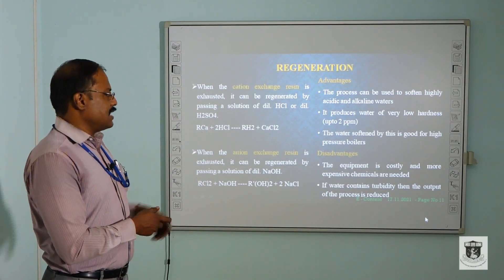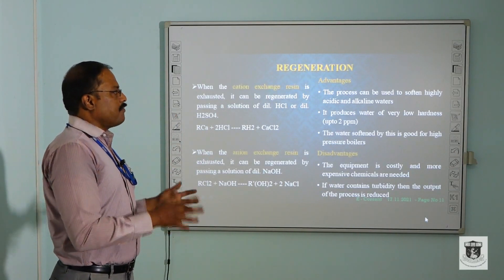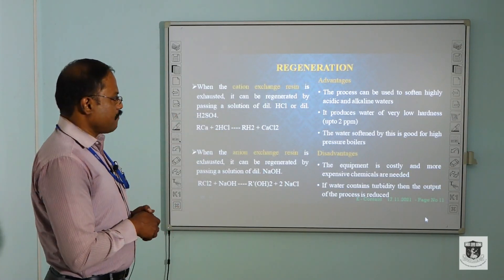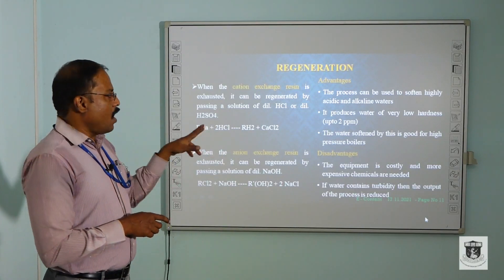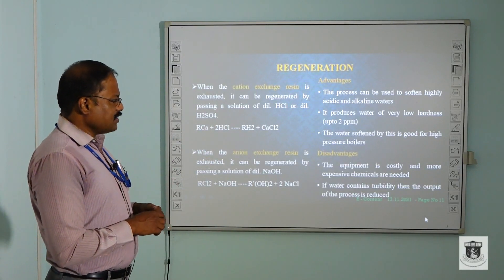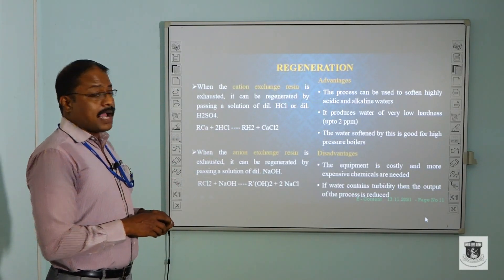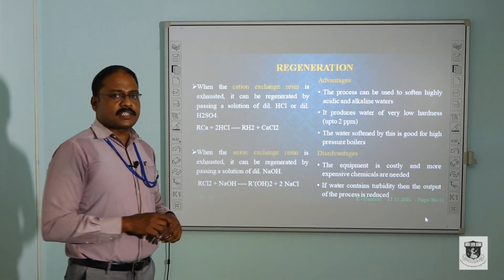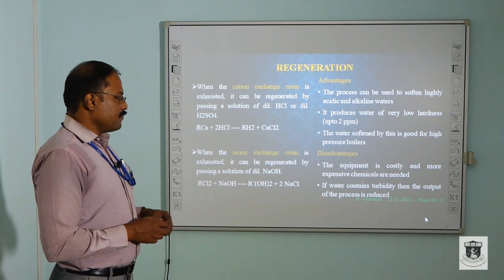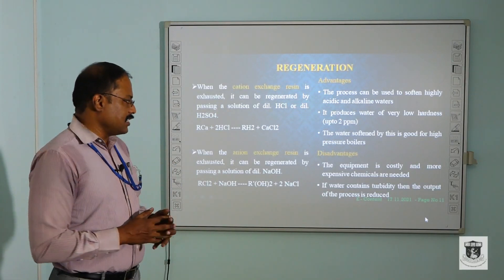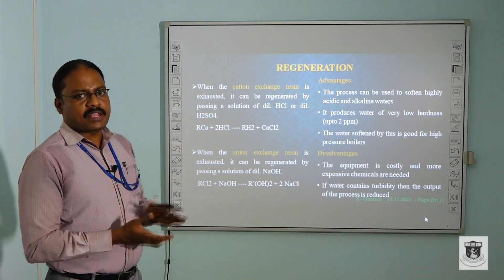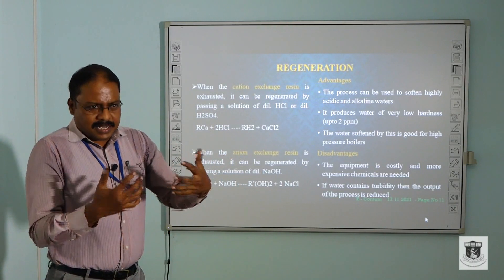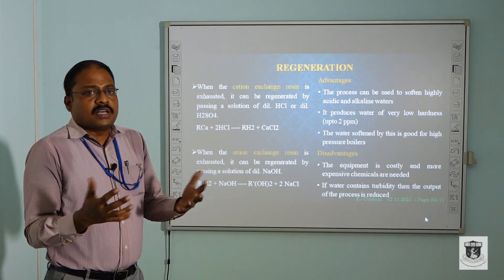Advantages and disadvantages of the ion exchange resin process: The process can be used to soften highly acidic and alkaline waters. It produces water of very low hardness, up to 2 ppm. Disadvantages: the equipment is costly and more expensive chemicals are needed. If the water contains turbidity, the output of the resin is reduced. Finally, these are all the important titles of water technology. At least we now know how we can remove the hardness from the water.